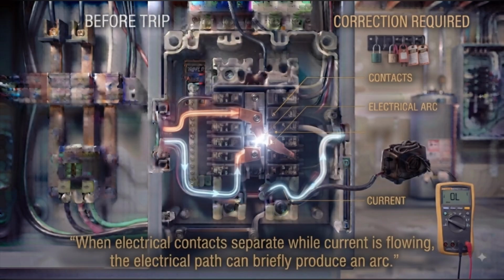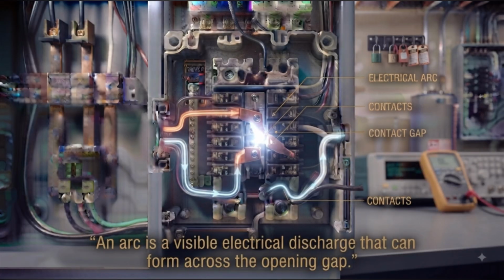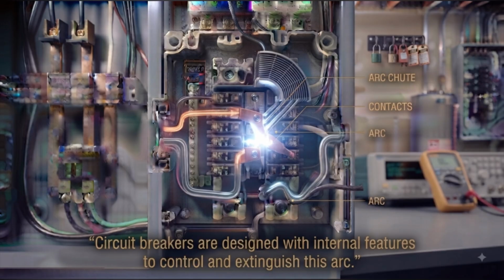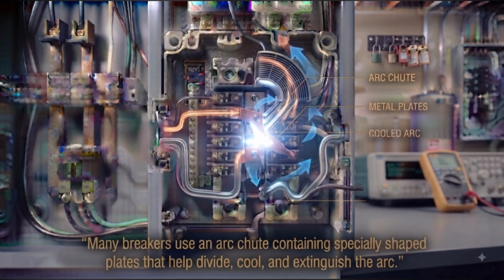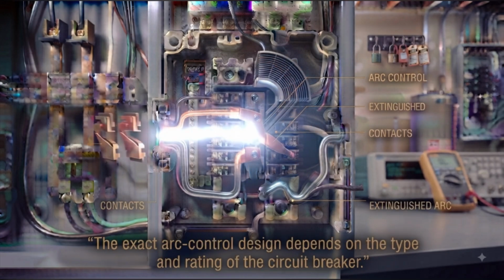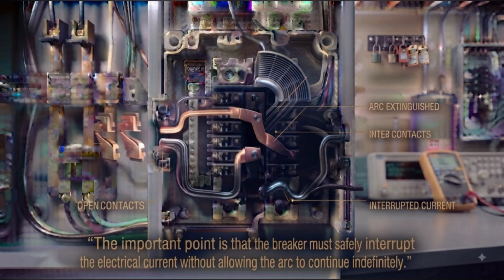When electrical contacts separate while current is flowing, the electrical path can briefly produce an arc. An arc is a visible electrical discharge that can form across the opening gap. Circuit breakers are designed with internal features to control and extinguish this arc. Many breakers use an arc chute containing specially shaped plates that help divide, cool, and extinguish the arc. The exact arc control design depends on the type and rating of the circuit breaker. The important point is that the breaker must safely interrupt the electrical current without allowing the arc to continue indefinitely.